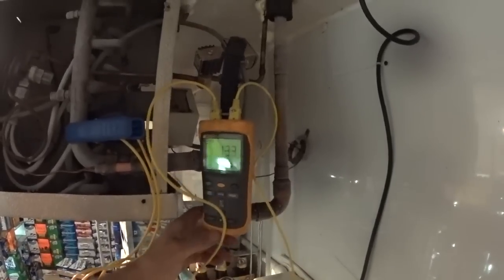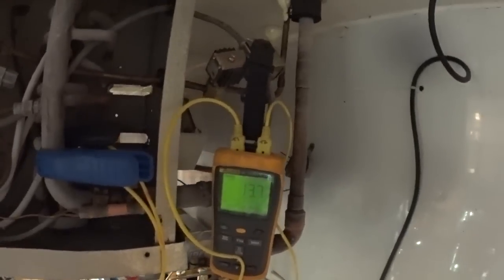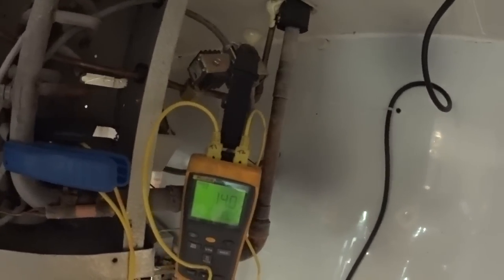But unfortunately, that's what I've got to live with right now. I've adjusted it as much as I could. Get it up to 14. A walk-in cooler like this, 15 is okay.